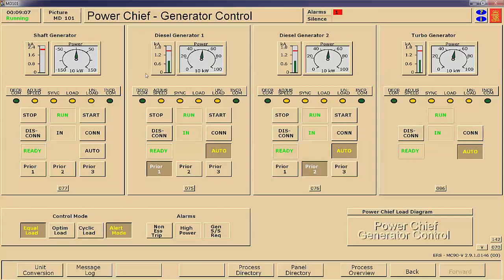One of the things to think about: diesel generator number 1 is burning clean distillate. Number 2 is burning heavy fuel oil off of the main fuel system, the same system that supplies fuel to the main engine. The turbo generator is being supplied steam from the oil-fired boiler, which is burning heavy fuel oil on its own fuel circuit. So all 3 of these generators are being supplied fuel from a separate source, so that if any one of them drops off the line for whatever reason, then the other 2 can pick it up.